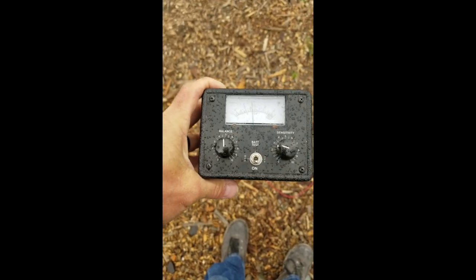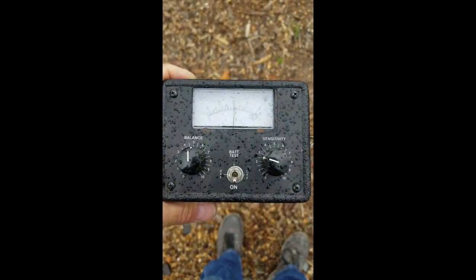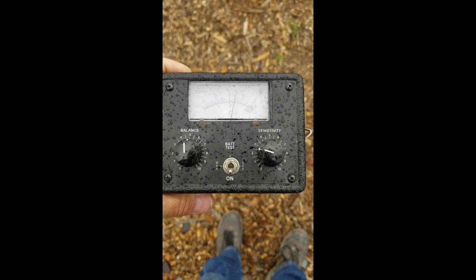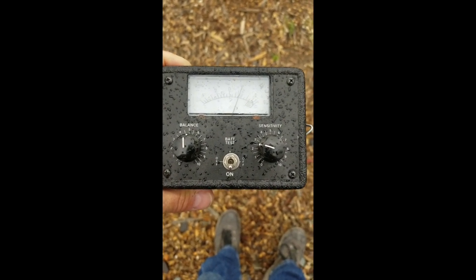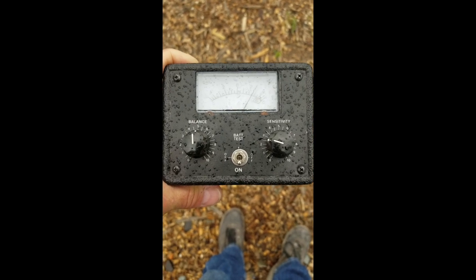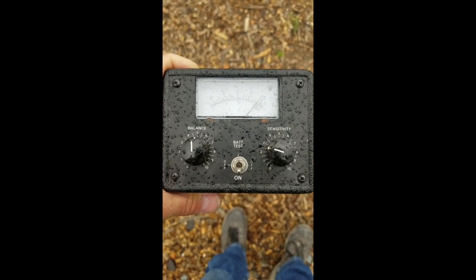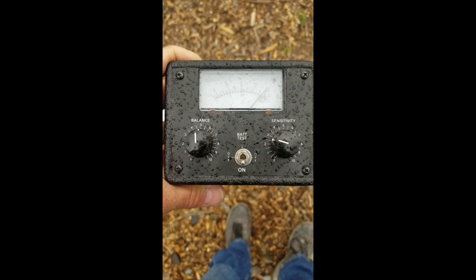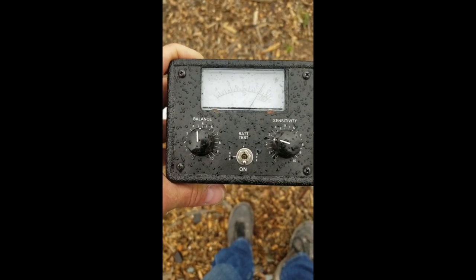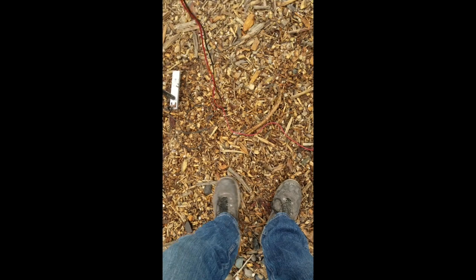I've moved my probes one more time. The black probe is now where the red one was. I've moved my red one over here, and now I'm getting a reversal. It's telling me the black probe is closer to the fault. So for me, there's probably 100 different ways to do this next procedure, but what I'm going to look for now is a null point. When I get my first reversal, I'm going to set this down. So I'm going to pick up my black probe, and I'm going to move it back the direction I just came. I'm going to move it back a couple feet, see what kind of a reading I get.